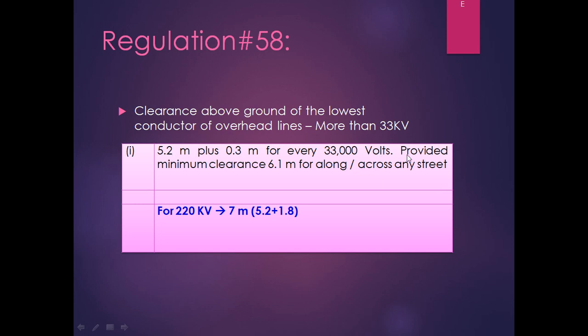For system voltage exceeding 33 kV, the formula is 5.2 meter plus 0.3 meter for every additional 33 kV. For 66 kV the clearance is 5.2 + 0.3 = 5.5 meter. It is also provided that the minimum clearance shall be 6.1 meter along or across any street. For 220 kV: 5.2 + (6 × 0.3) = 5.2 + 1.8 = 7 meter. Since 7 meter exceeds 6.1 meter, this 7 meter applies along a street, across a street, or ground where no street is involved — the limit is the same for all.